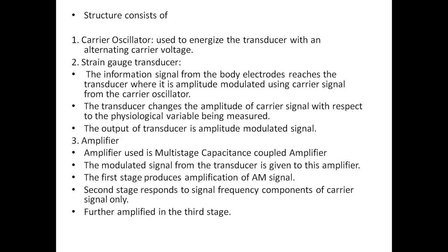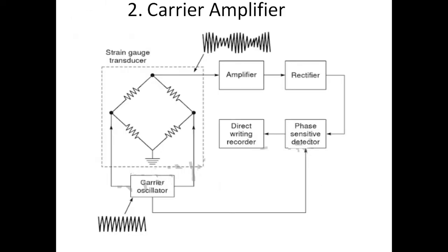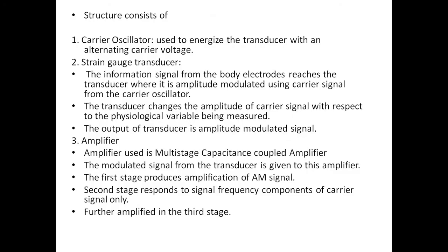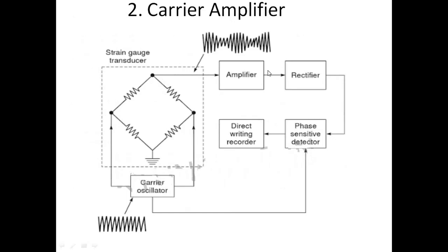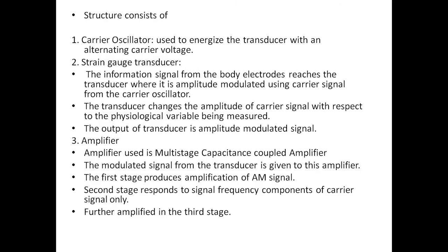Next is the amplifier stage. Here a multi-stage capacitance coupled amplifier is used. The modulated signal from the transducer is given to this amplifier. The first stage produces amplification of the AM signal, the second stage responds to the signal frequency component of the carrier signal only, and this is further amplified in the third stage — a multi-stage capacitance coupled amplifier.